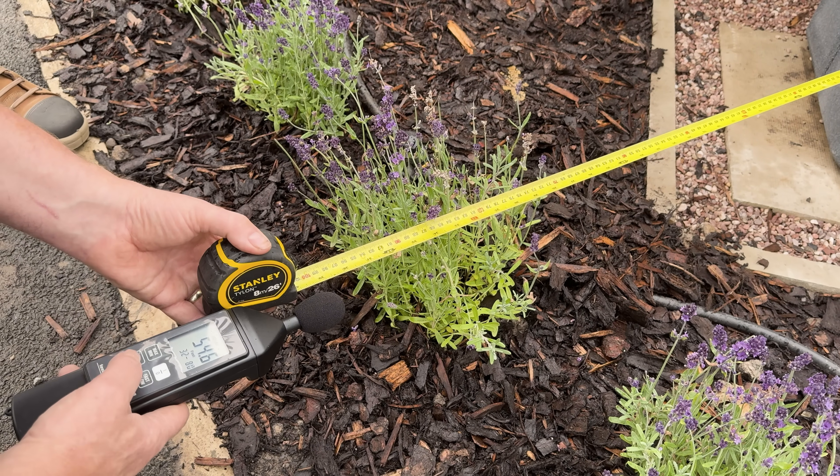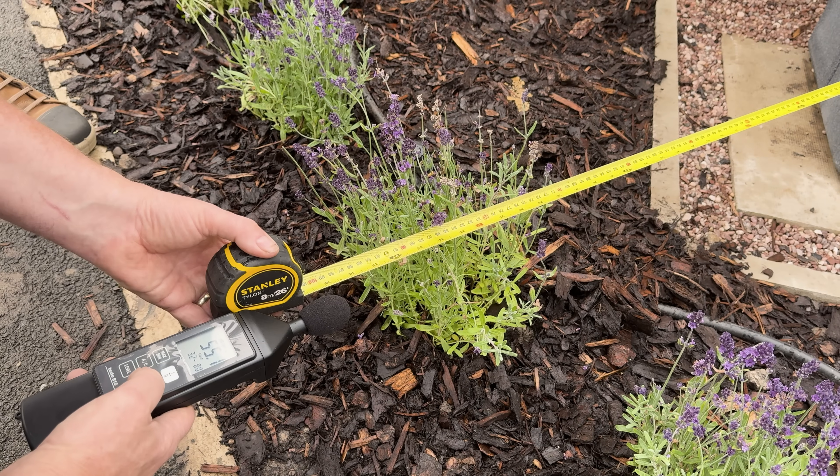Before anyone starts in the comments saying that means everyone's going to hear your heat pump because it could be closer to their house — yes, in theory you could be right. But heat pumps very rarely make any noise; they are very, very low in noise. Luckily they have changed the noise calculation levels too. It's dropped from 44 decibels down to 38 decibels — I've put the exact figures in the description. They've also changed the way it's calculated, which can be slightly beneficial to some and less so to others, but effectively they don't want neighbours to be disrupted. The new system calculates noise disturbance more fairly and accurately than before.